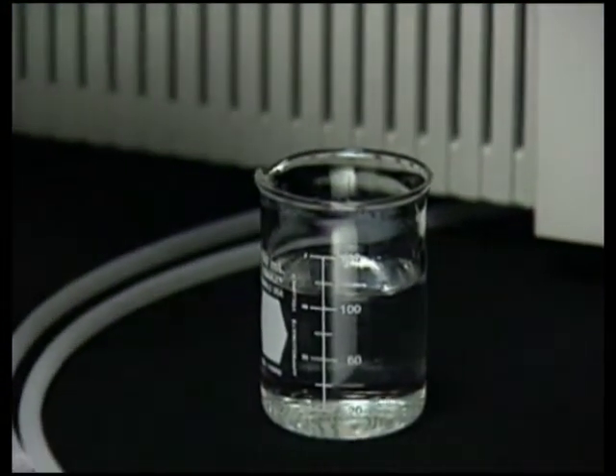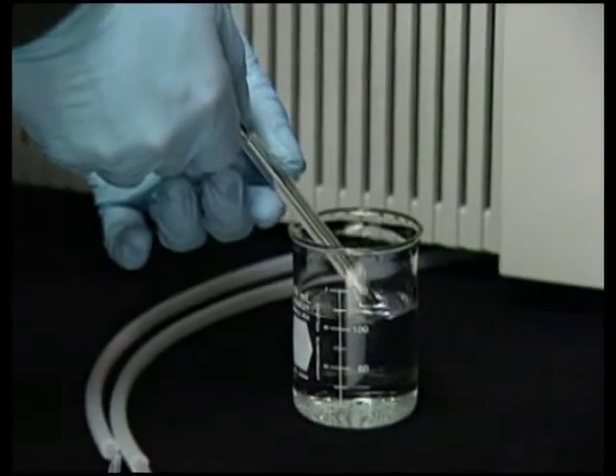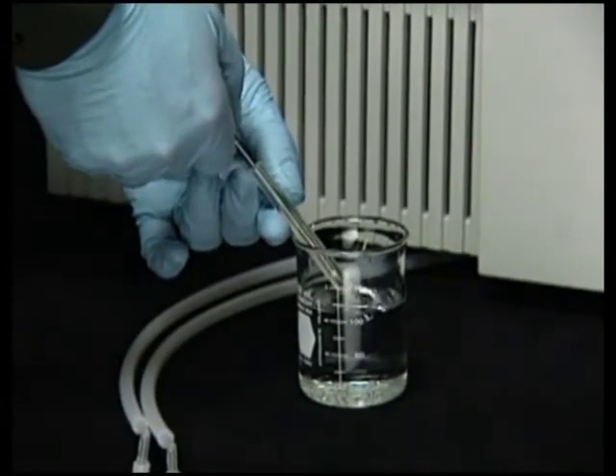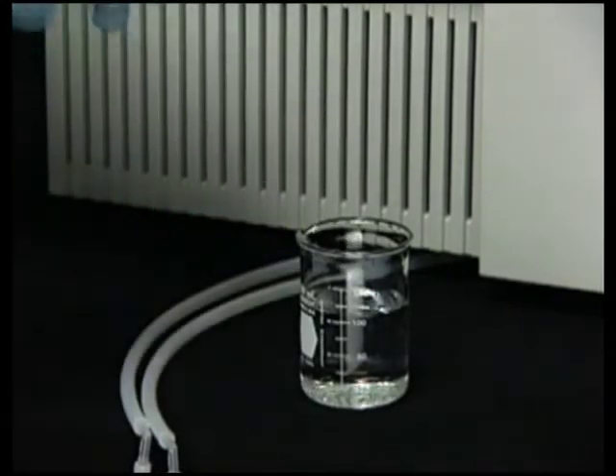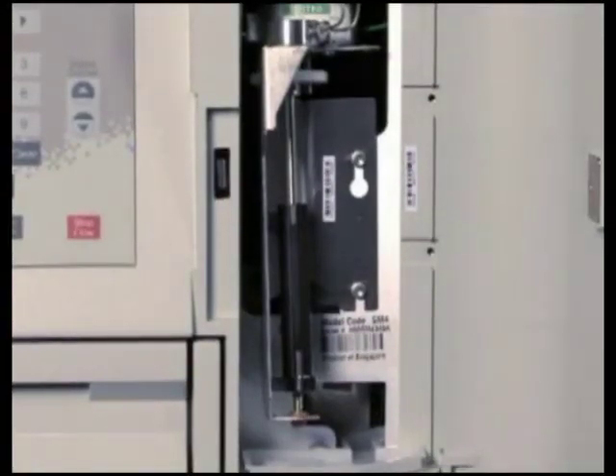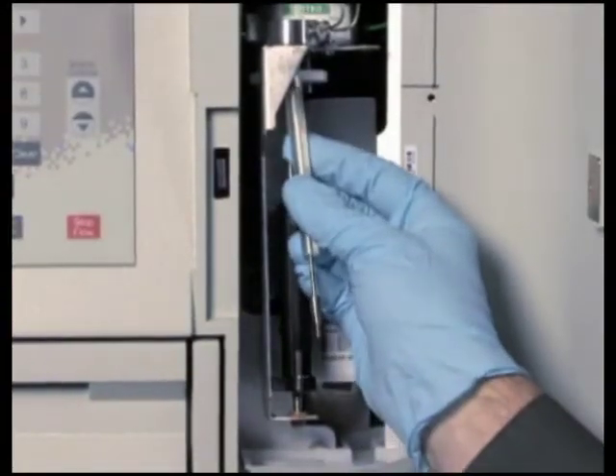Before you insert the syringe into the mounting bracket, partially fill the new syringe with mobile phase to help remove air bubbles. Screw the new syringe partially into the syringe drive mounting block. Do not tighten.